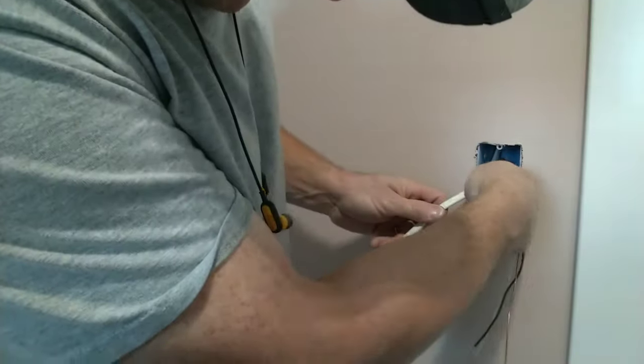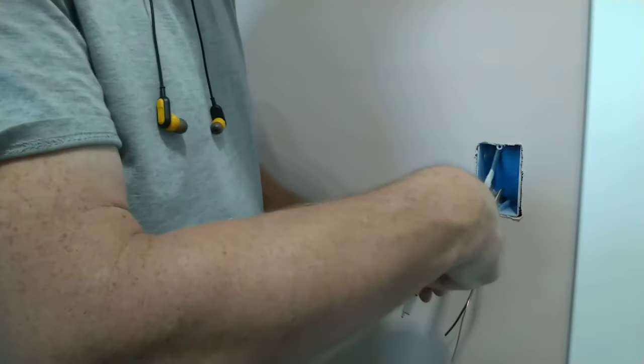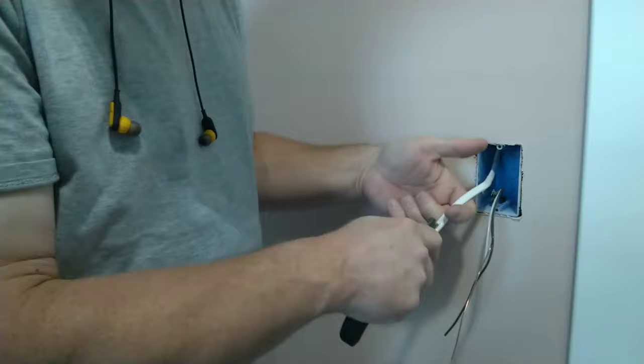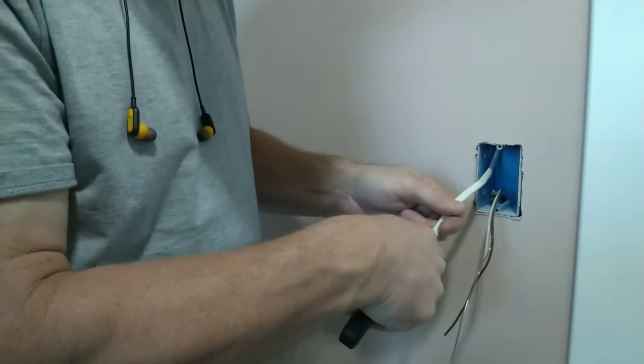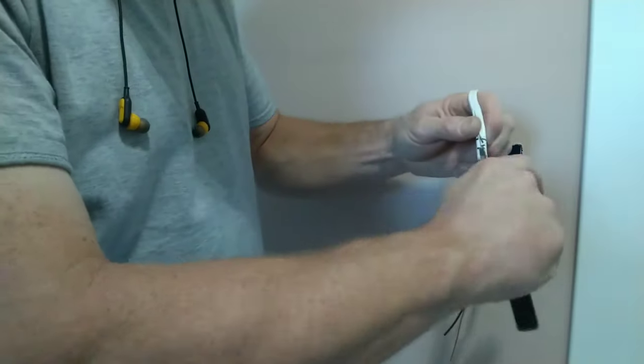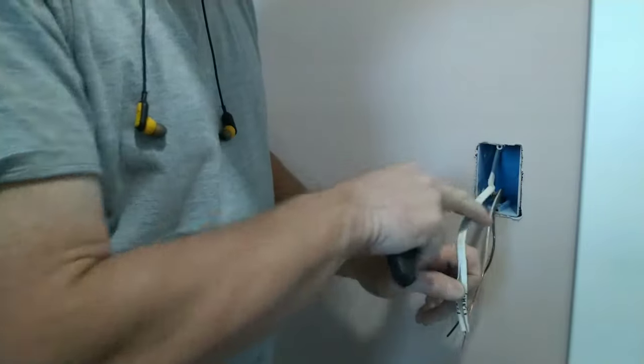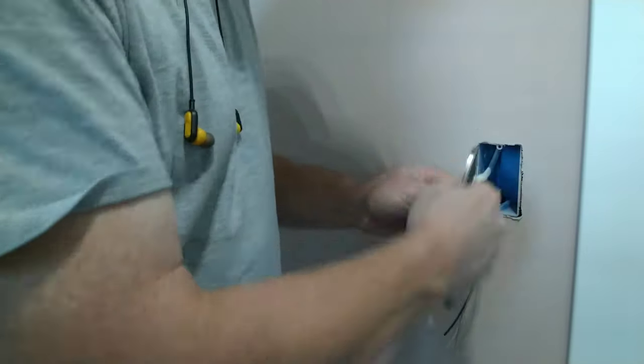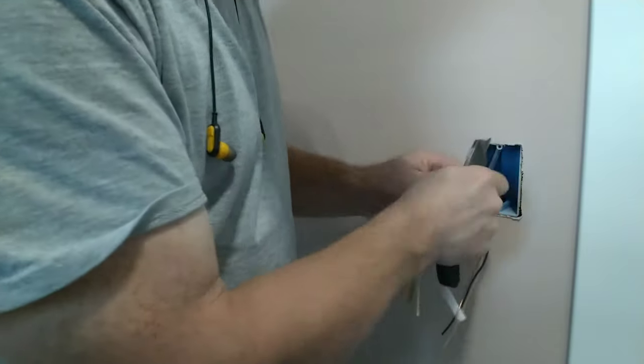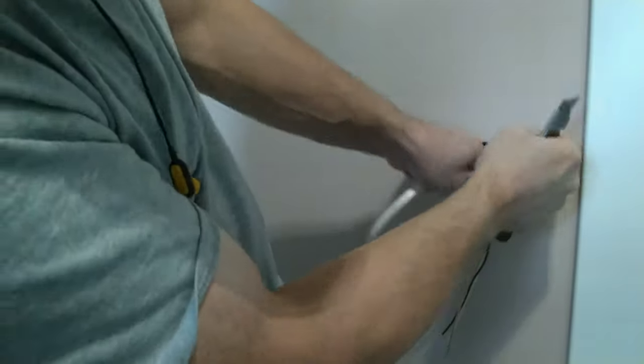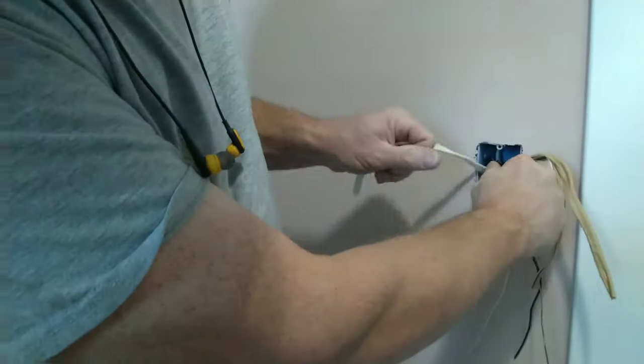So starting 3/4 inch from the back, I'm scoring down the wire. I'm sliding my hand up past my blade, and then I'm continuing my cut. When you get down to the end, you can slice heavy. On this part of the jacket, you want to slice really, really light, barely scoring the jacket, so we're not cutting, we're scoring.